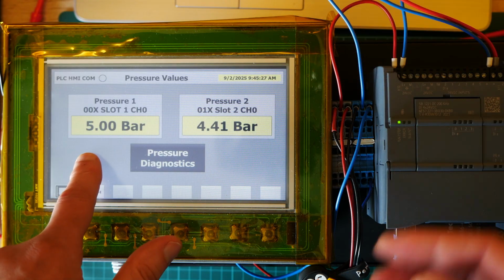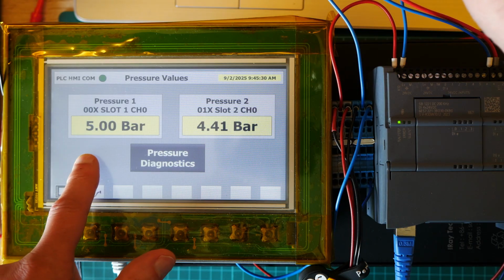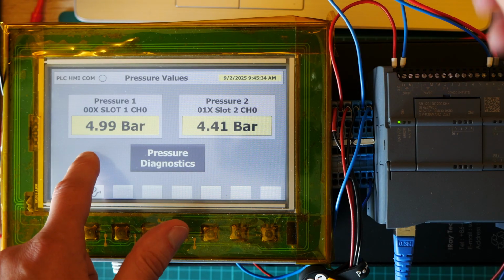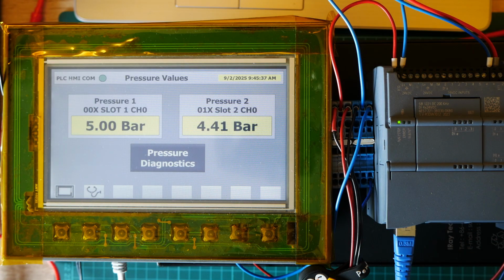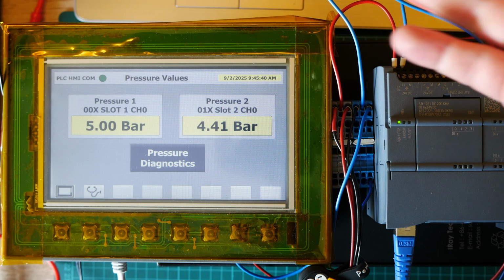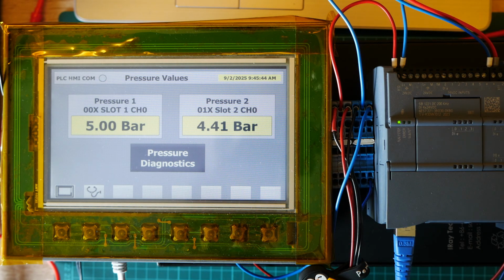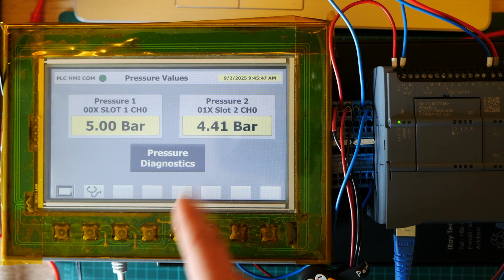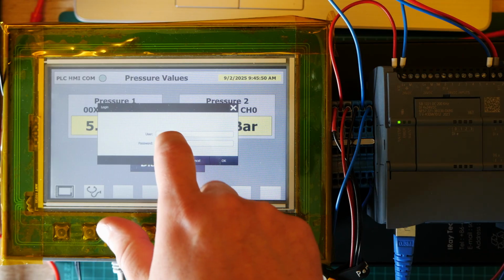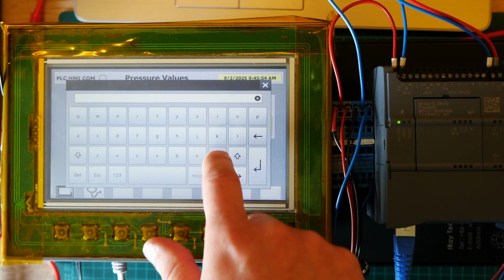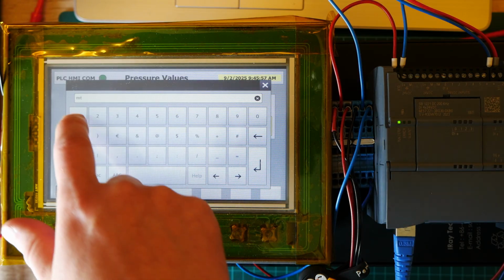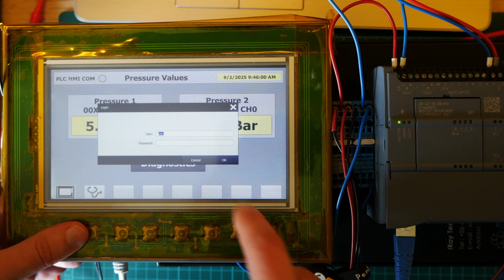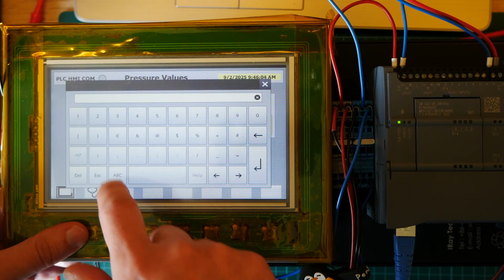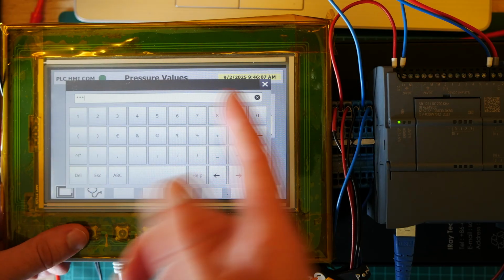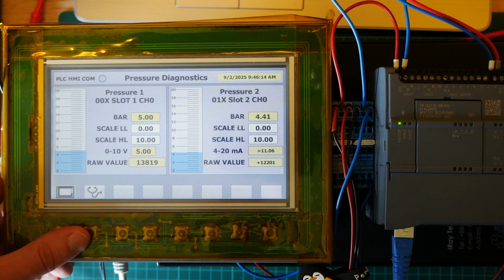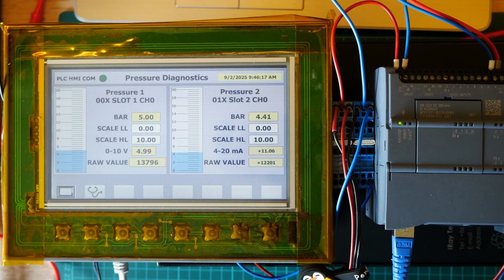we have 5 bars. Okay, because right now I hooked up my bench power supply here. I don't have an actual sensor. So from my power supply I send 5 volts and this shows 5 bars. Now it's a good idea to have some sort of diagnostics inside the HMI panel. But some of these diagnostic settings should be only for electricians, for maintenance. This information is not useful for the operator.